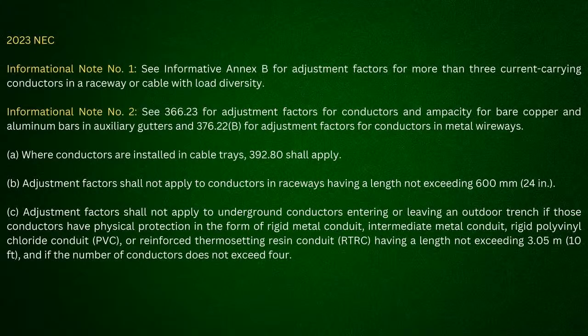The one thing that I think is interesting though is when you look at that installation, I don't really see that being any big problem. You have some NM cables coming into a piece of 2-inch PVC. The PVC is large enough for those Romexes to come in. But I'll take it a step further. A lot of times when we're doing gas and oil and stuff, we're just packing these sleeves with cables, and when you talk about that load diversity, we're using ladder logic, so these aren't running full continuous loads through these sleeves. So I think that's why they had to have that ambiguity in there to allow you to do that, because we're not going to sit there and run 20 separate conduits out there for some of that stuff, because it's not all running at the same time. Sure. So that's a good point.